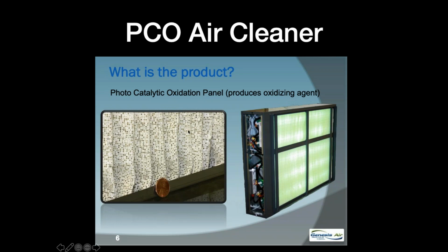The hydroxyl radicals have a life of 10 to the minus 9th seconds. So they're created and die very quickly, so they never leave the surface of that media. You can see the UVC lights. You see the white through here. Those are your UVC lights. This panel is drilled through the center, and we run the lights through the center of that. It's called center point PCO. There are a lot of different forms of PCO out there, but this is called center point PCO.